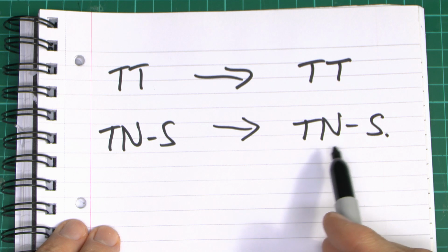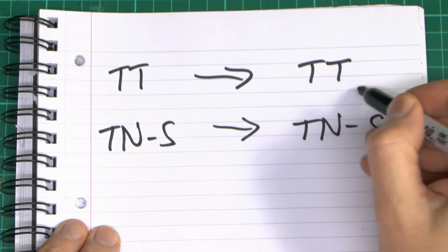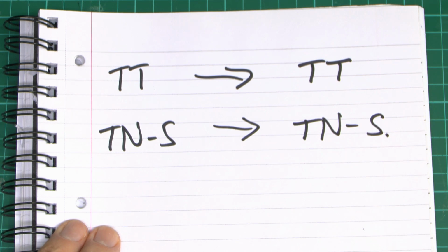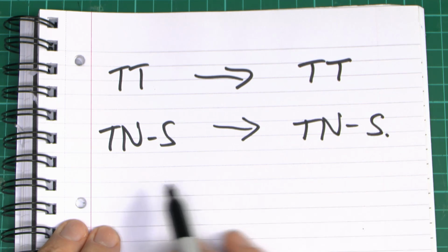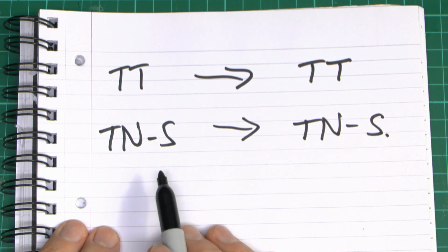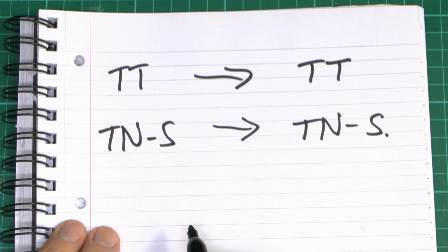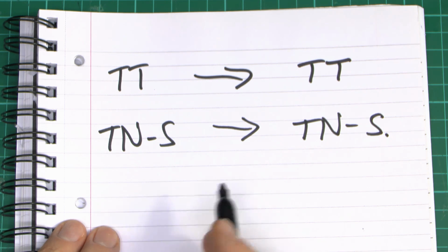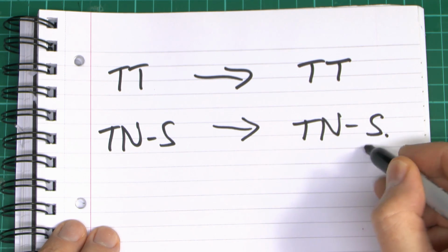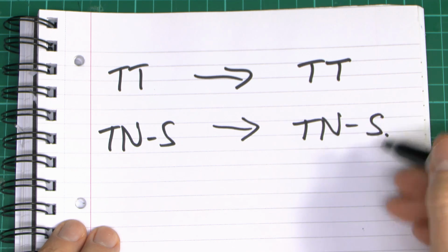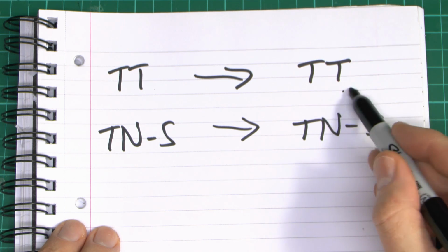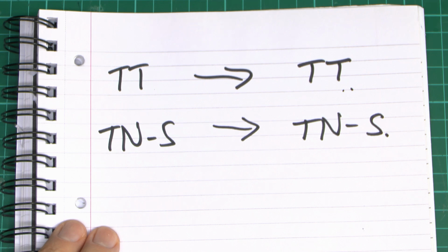You could, of course, not use TNS. You could, of course, just put an electrode in and use it as a TT installation. This may be worth considering, because a lot of the older ones are being upgraded or changed, and when they're upgraded or changed, they inevitably end up as TNCS. So, although you can use the TNS earth connection, it may be worth doing it as a TT anyway, just to avoid any problems in the future.